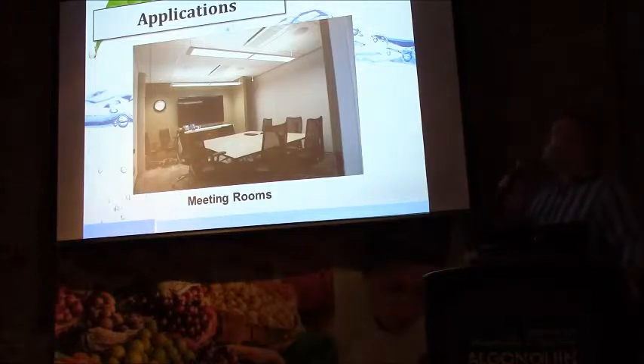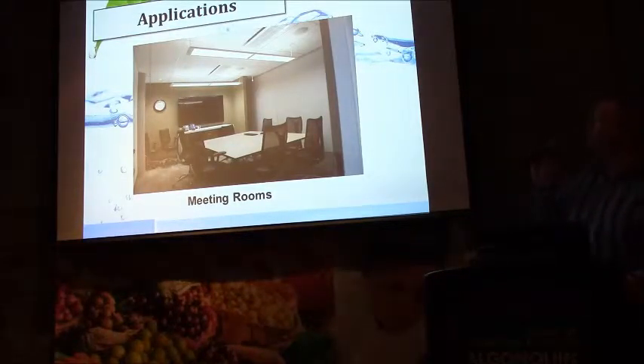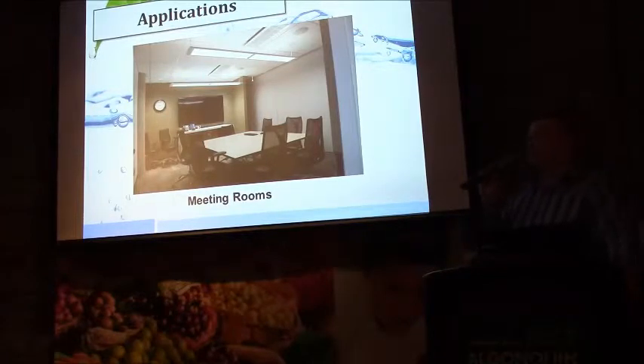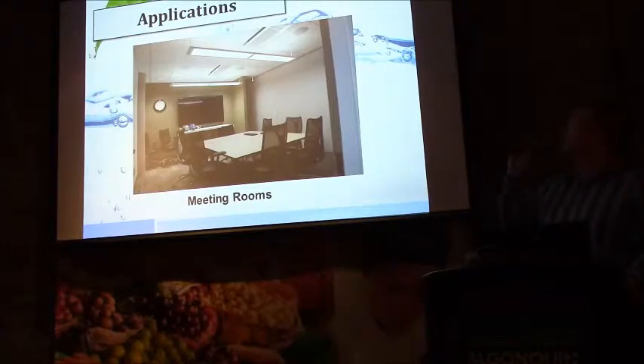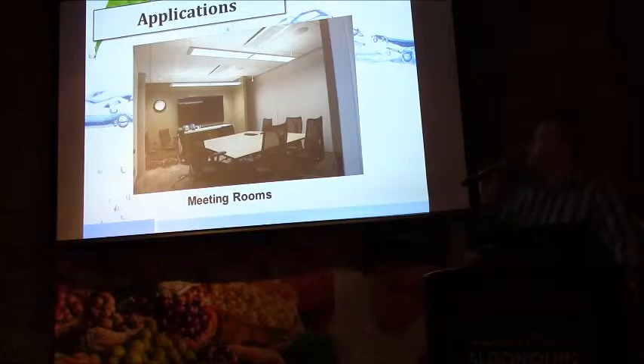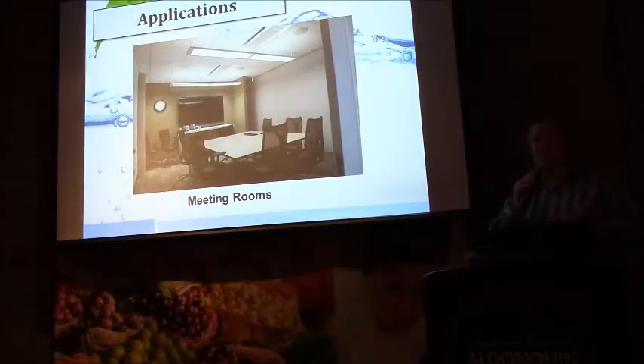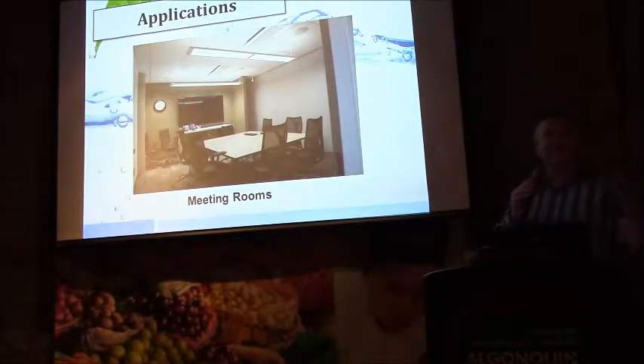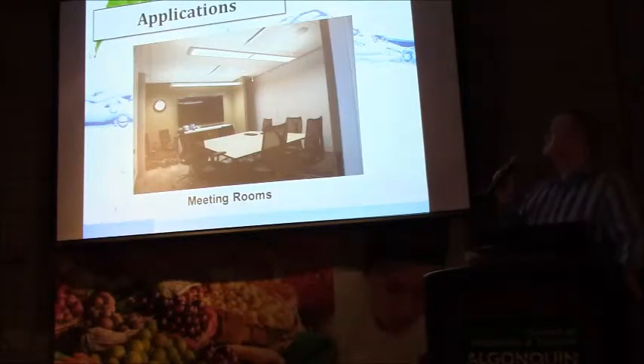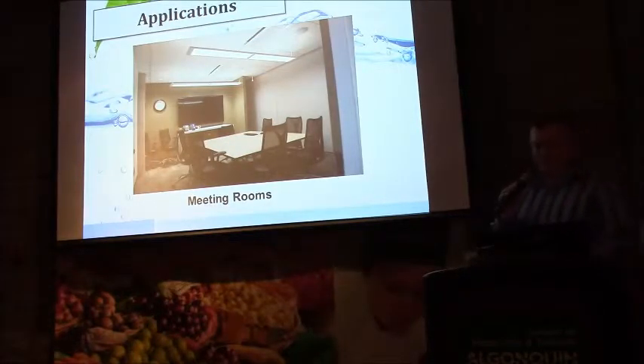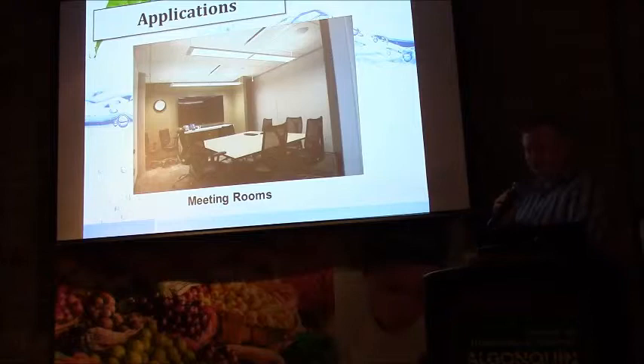A boardroom or a little meeting room. The configuration of the lights in this instance was crosswise to the discharge of the beam. That was done intentionally to ensure that the air passed across the thin cable that hung down from the ceiling. Also seeing these installed where the lights extend beyond the beam, directly underneath of it, and so the beam becomes a local capture point for the sensible heat that flows off the back of the lighting fixture, which is fine. It actually provides overall net more capacity, but it's not factored into the selection process.